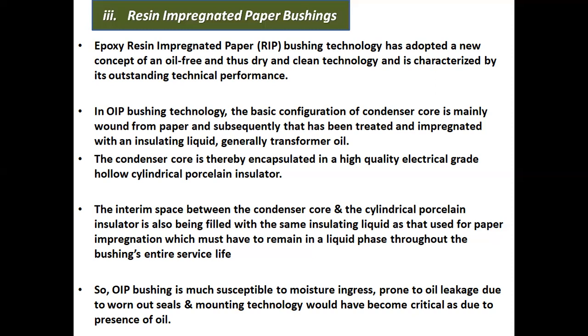So OIP bushing is much susceptible to moisture ingress, prone to oil leakage due to worn out seals, and defects in mounting technology would become more critical due to the presence of oil.